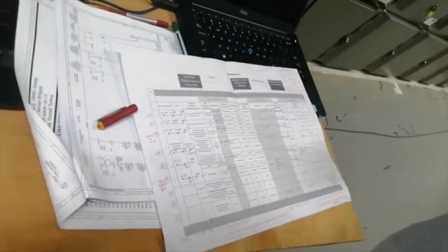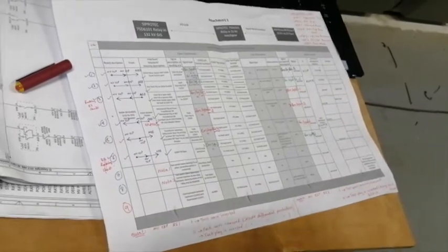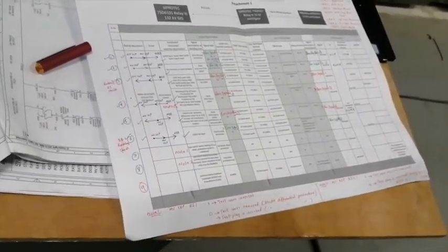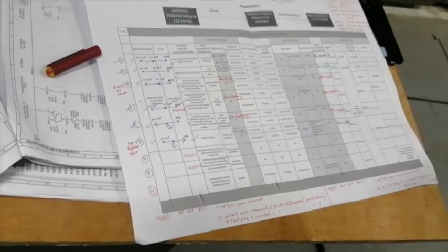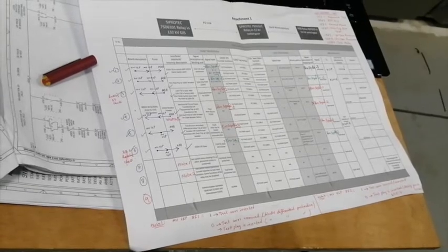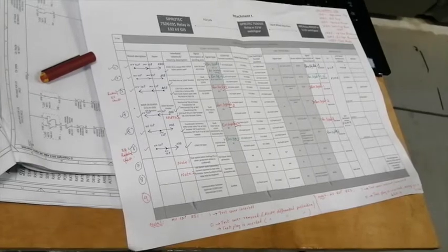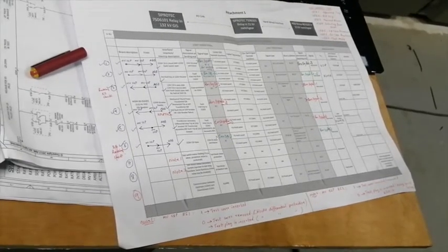Three are going from the 11 kV SIPROTEC relay to the 132 kV side, and 3 are coming from the 132 kV side to 11 kV. Two signals are related to the local test plugs, and the 9th signal is for communication failure. We have checked all these signals. We have simulated the complete path of these signals, starting from 132 kV all the way up to the 11 kV SIPROTEC relay and also the 11 kV ABB relay, to check the actual interlocks with the switchgear. So this completes our testing of the interface signal list.